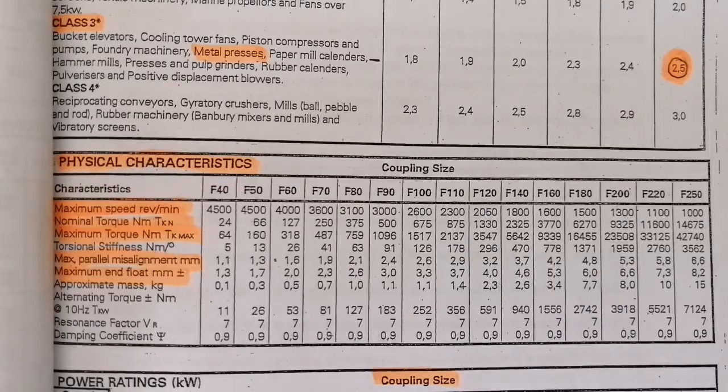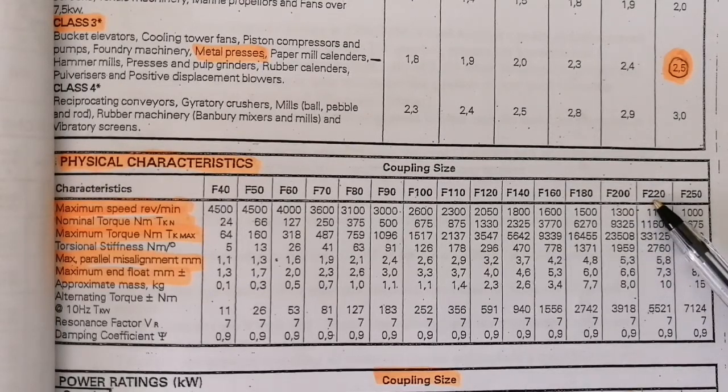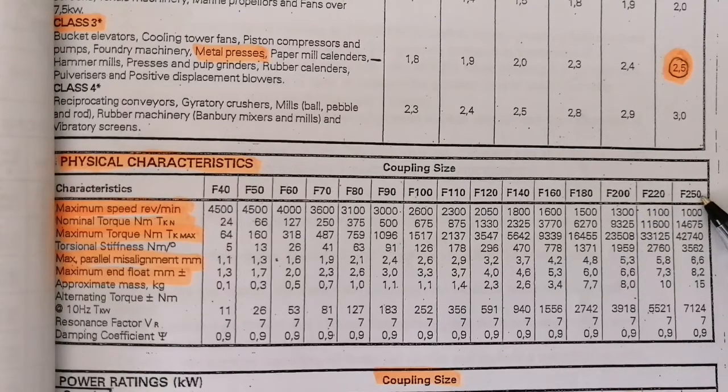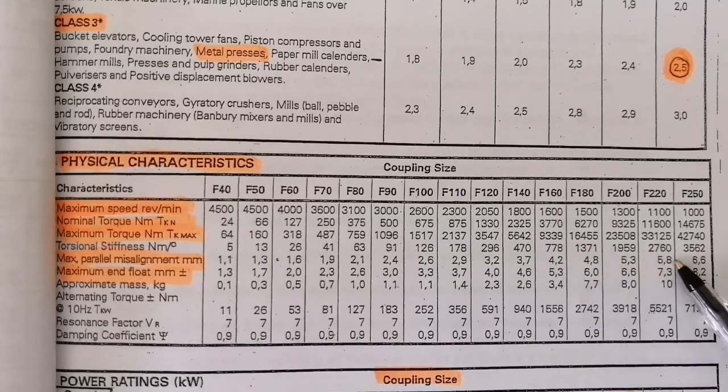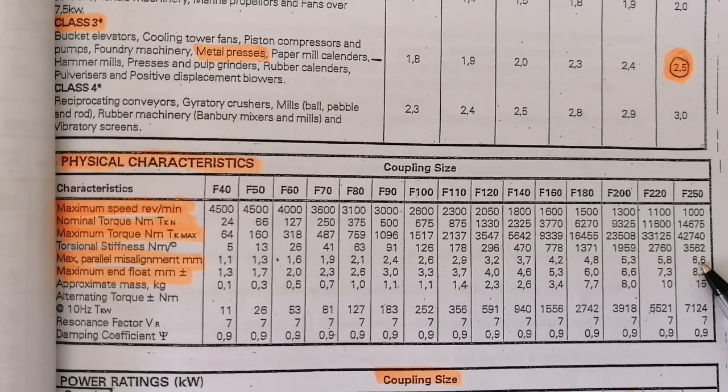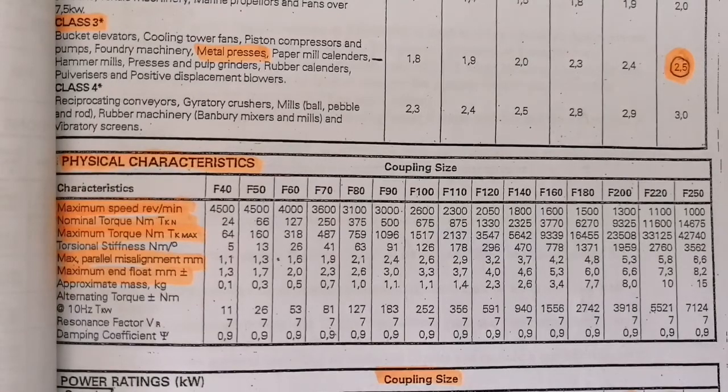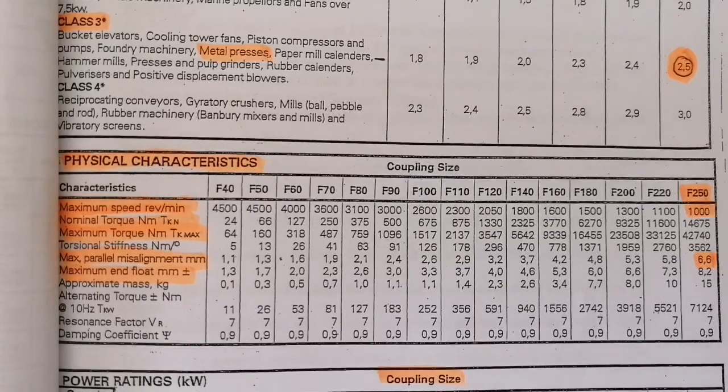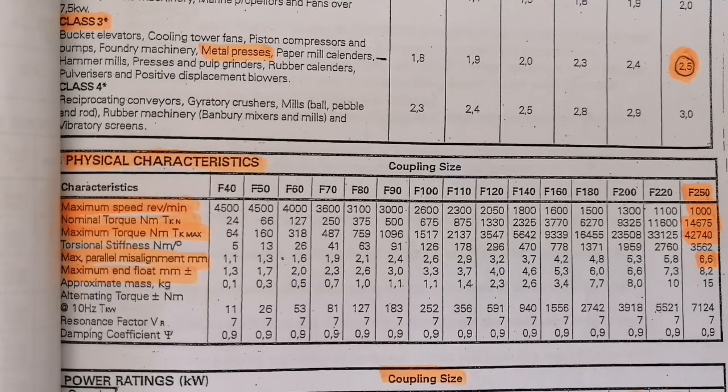Now let's revisit the maximum parallel misalignment. We know that the F200 and F220 cannot handle that type of misalignment. So the next thing to do is go to the next higher coupling and see what it can handle. Let's look at the F250. Looking at the maximum parallel misalignment going across, we've got 6.6 millimeters and it's more than required - we require only 6. All the other characteristics are in check: the maximum speed, the nominal torque, the maximum torque, and of course the end float which is 8.2 millimeters.